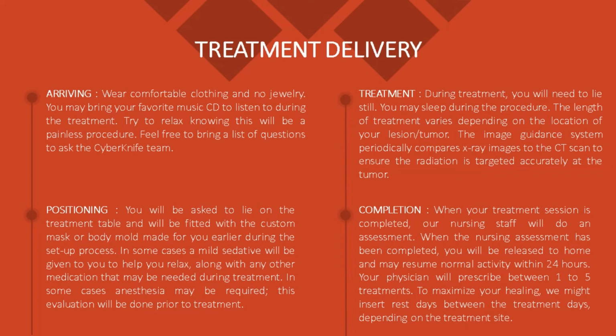The imaging system acquires the first set of X-rays in the treatment position. The table then adjusts to provide the necessary millimeter alignment, and the robotic arm then moves the linear accelerator to its first position and delivers the first treatment beam. This process is repeated many times as the X-ray system reacquires the target and the robotic arm realigns the linear accelerator from multiple different positions, often greater than 100 times. At each angle, the precise radiation beam is delivered.